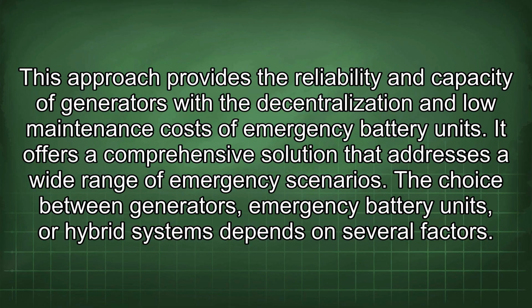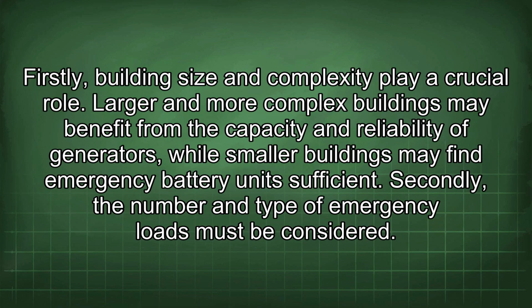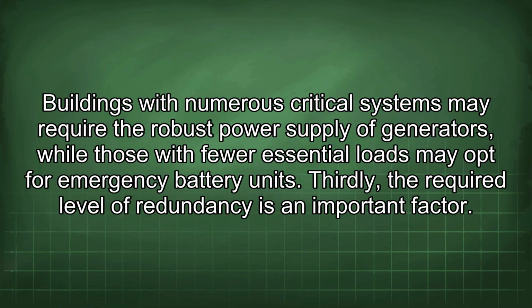The choice between generators, emergency battery units, or hybrid systems depends on several factors. Firstly, building size and complexity play a crucial role. Larger and more complex buildings may benefit from the capacity and reliability of generators, while smaller buildings may find emergency battery units sufficient. Secondly, the number and type of emergency loads must be considered. Buildings with numerous critical systems may require the robust power supply of generators, while those with fewer essential loads may opt for emergency battery units.